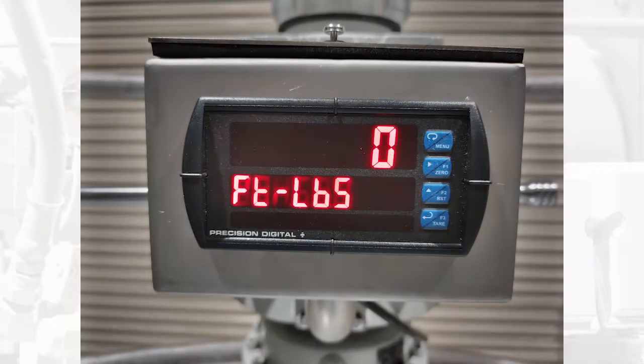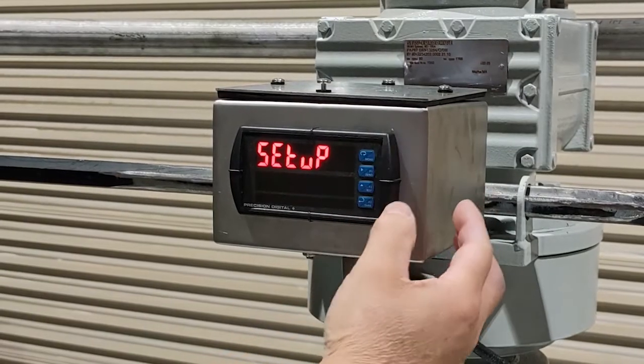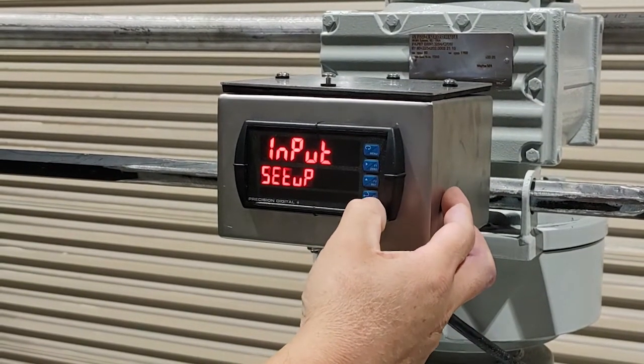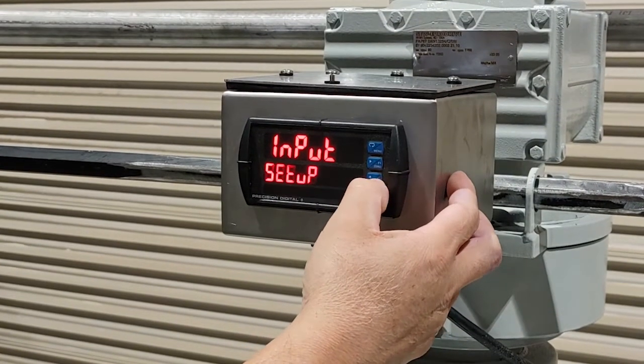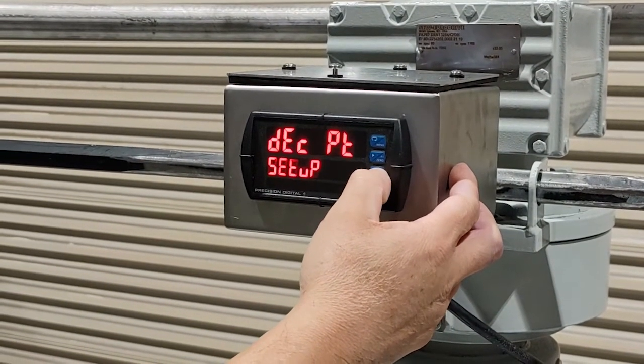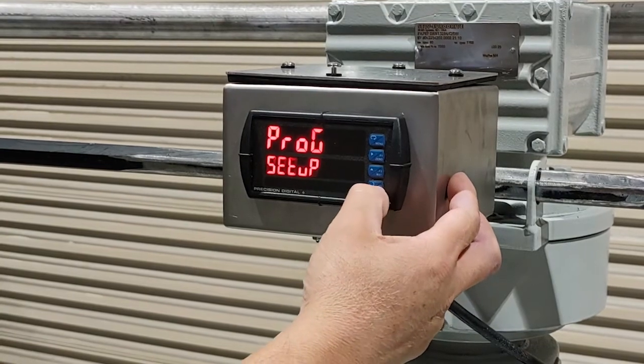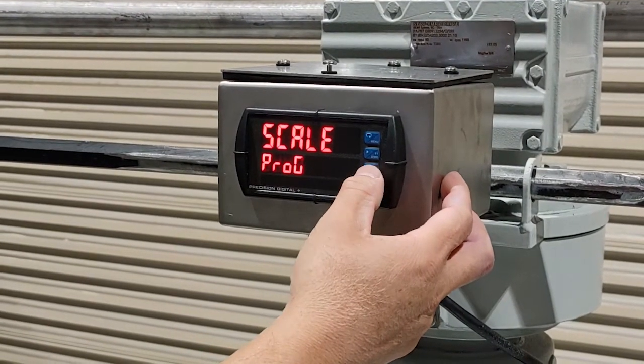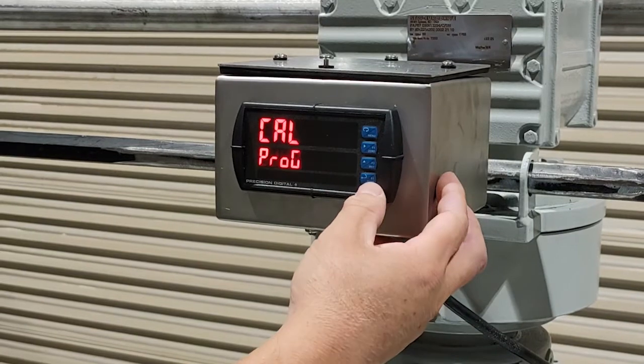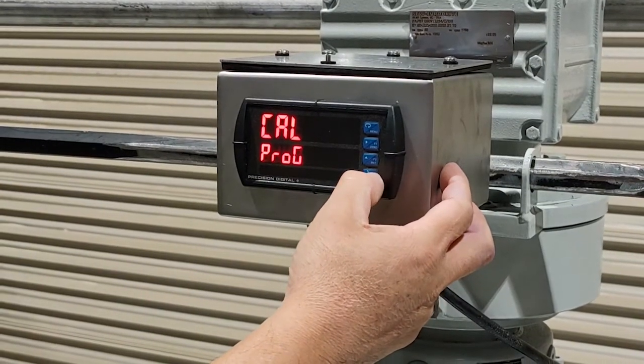On the faceplate of the indicator, there are 4 buttons: Menu, Next, Scroll Up, and Enter. To begin the calibration process, you will need to set the indicator to calibration mode. Press the Menu button once, and then press the Enter button to enter the setup mode. Press the Scroll Up button 3 times. Press the Enter button to enter the program mode. Press the Scroll Up button once, and press the Enter button to enter calibration mode.